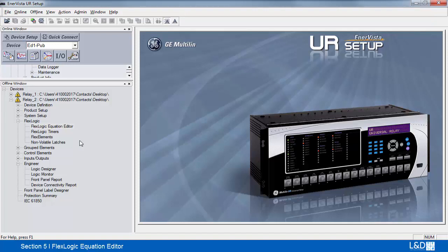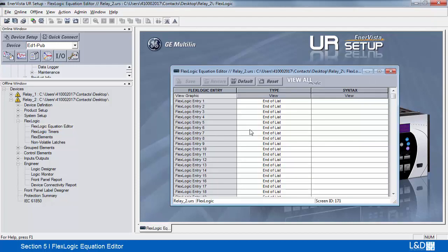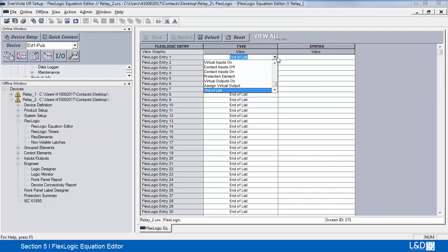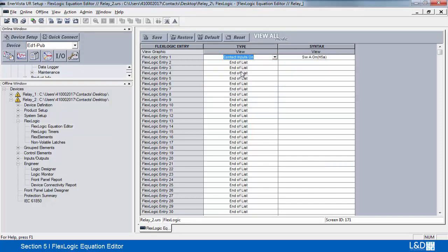To create a circuit using the FlexLogic Equation Editor, double click on it, and we're going to generate two inputs. We're going to add them together to generate a virtual output. Now, this is using the reverse Polish notation.